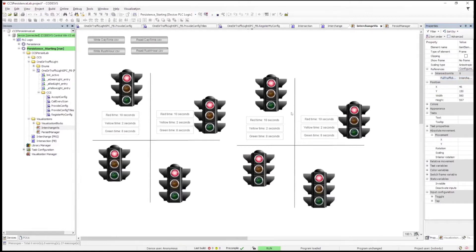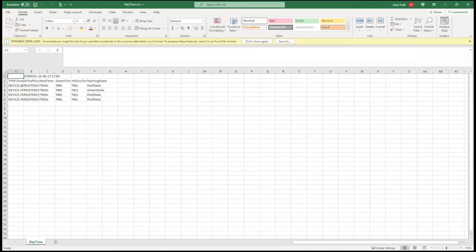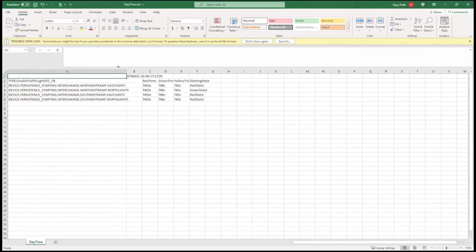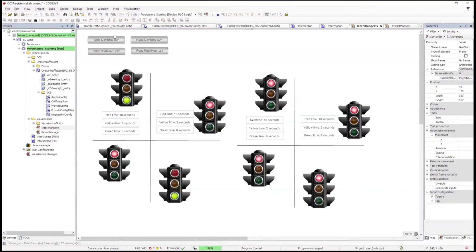The south ones will not be working right because they haven't been configured, but that's not a problem. We make sure we're on daytime, and we write the daytime file — you see all green, not good. We go back to our CSV file, open up the daytime. You'll notice the two additional instances of the lights are here all automatically. It still has the default for the light — default for any light is red state. We'll change that back in, then do a warm reset or just say read, and now everything will be correct for both sets of lights.